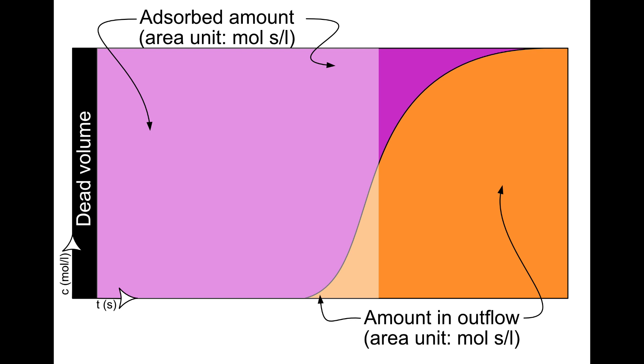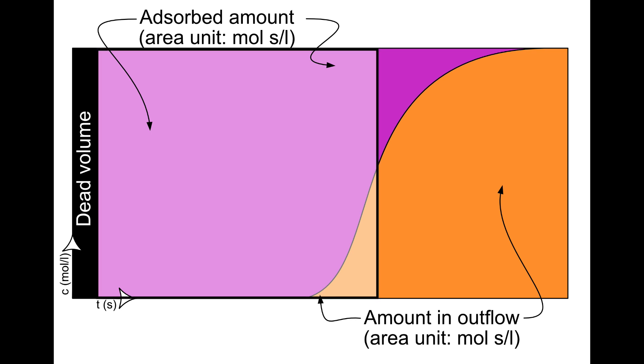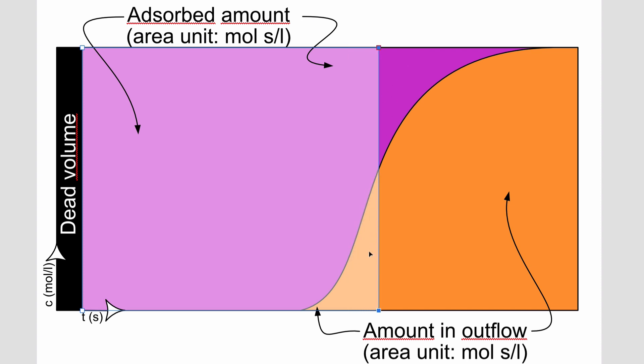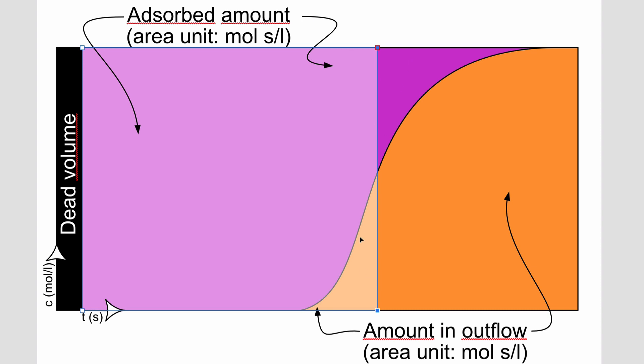We're looking for a rectangle that has the same area as the purple area. If the rectangle is drawn in a certain position, it does not cover the dark purple area at the top — that is part of the capacity of the column — but on the other hand, it includes the light orange area at the bottom, which is not part of the capacity. By changing the length of the rectangle, the relative size of the dark purple and light orange areas change. When the dark purple area not included in the rectangle equals the light orange area included in the rectangle, we have found a rectangle with the same area as the entire purple area. The length of this rectangle is measured in time and we call it T star.